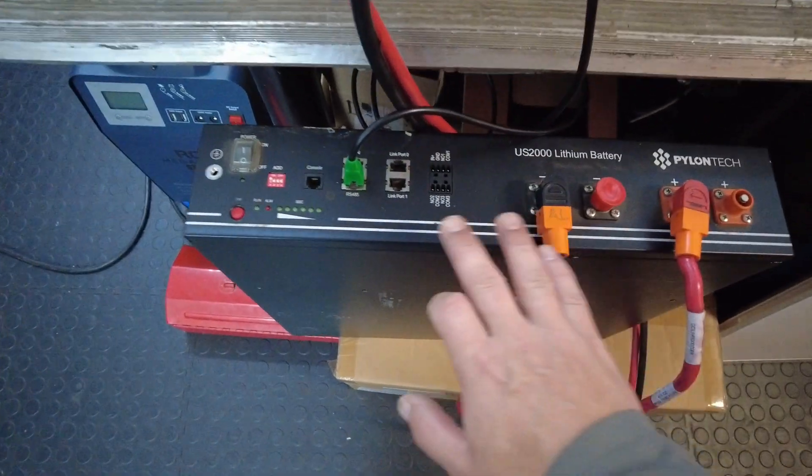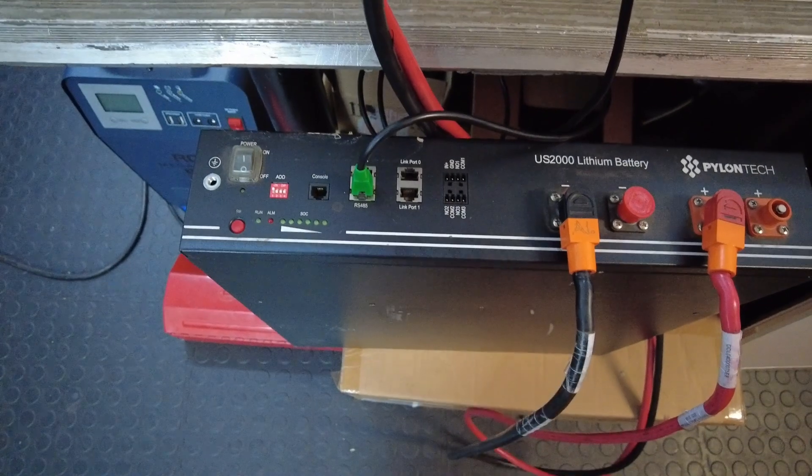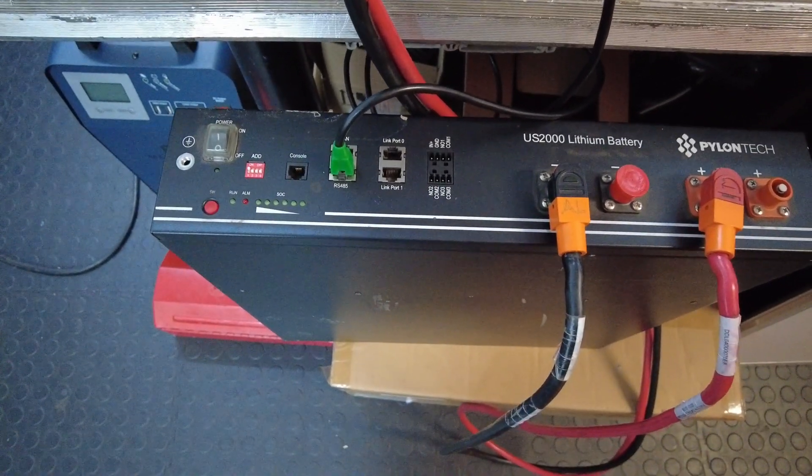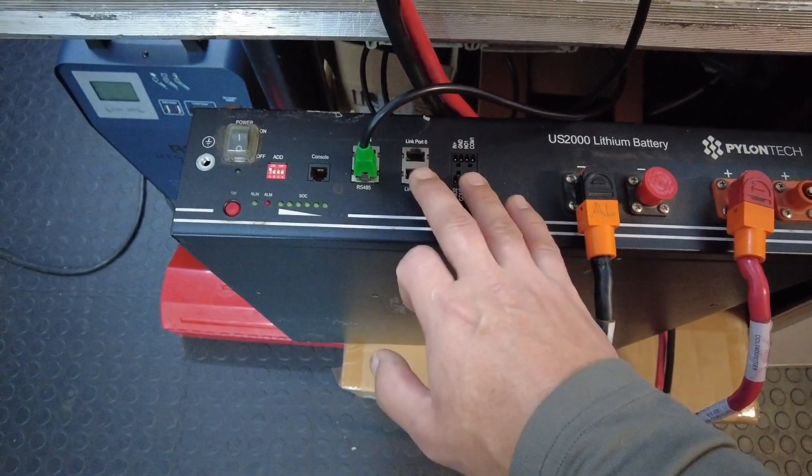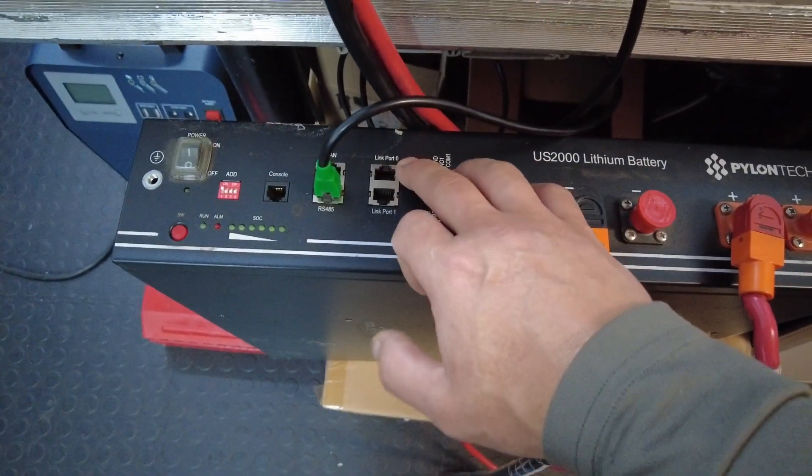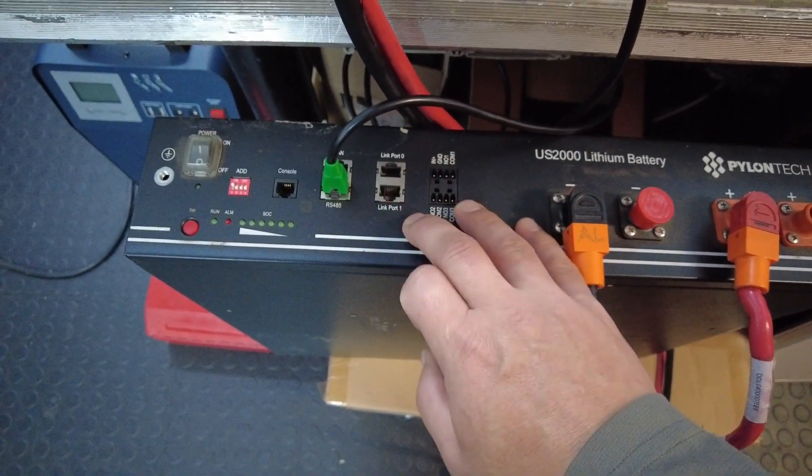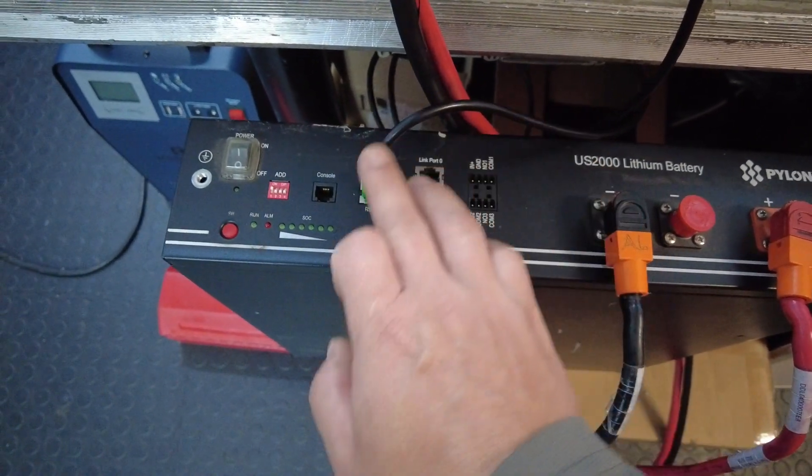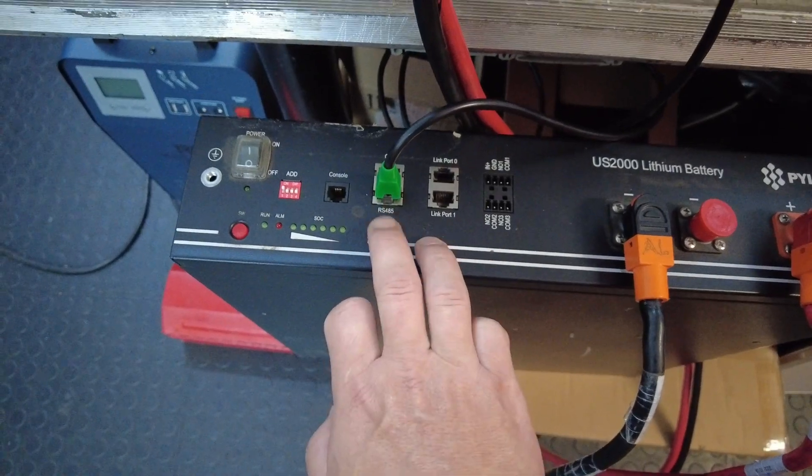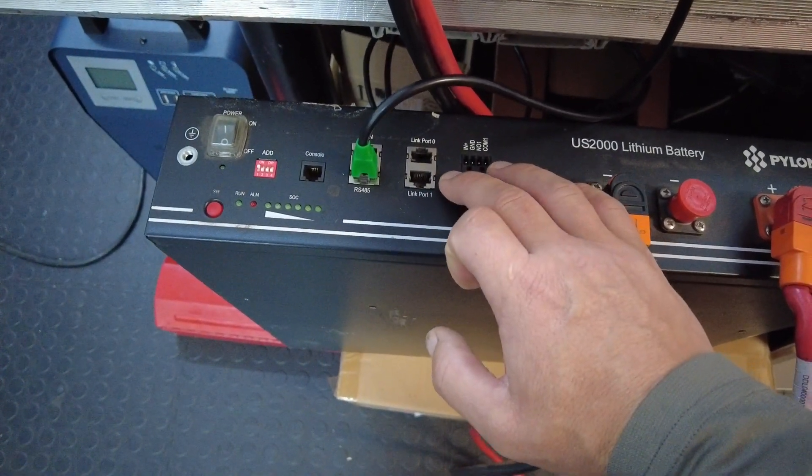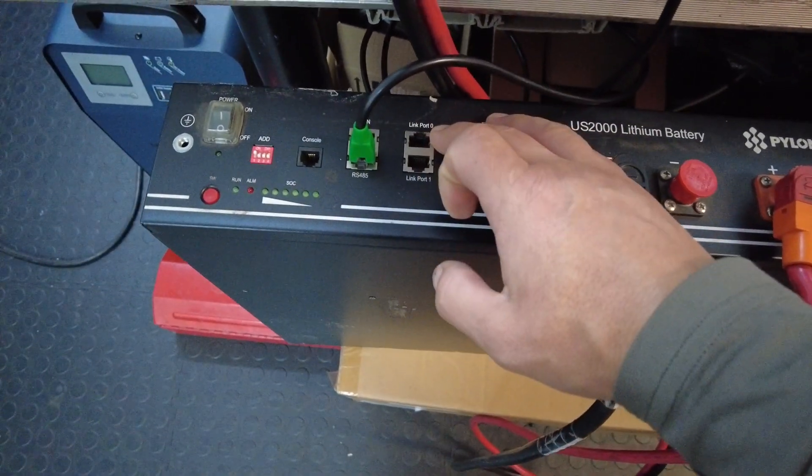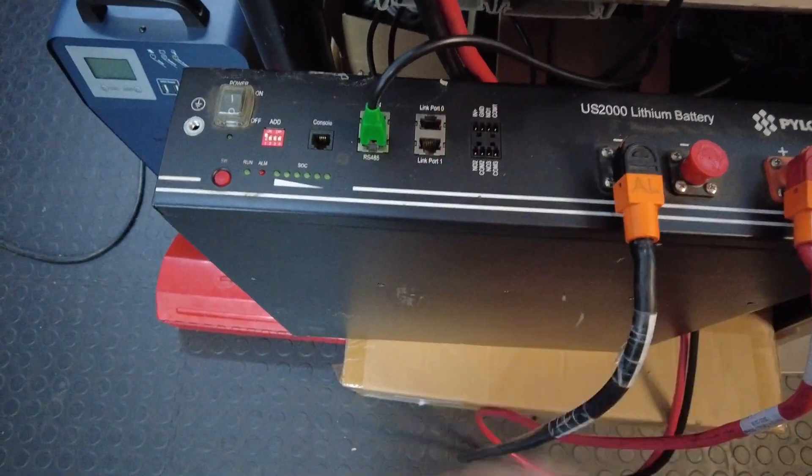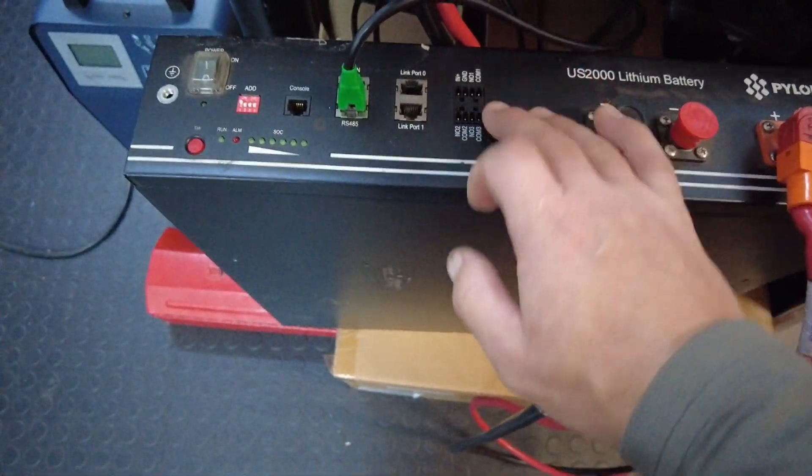In this case I'm only using one battery which is my master. Just keep in mind should you connect more batteries in parallel with this one, you do need to establish communication between them as well. Note you have a link port zero and link port number one. You will have your incoming networking cable from the inverter to your RS-485 port, then from link port number one you will jump to the next battery to link port zero and so forth. It will go link port one to zero, one to zero, one to zero.